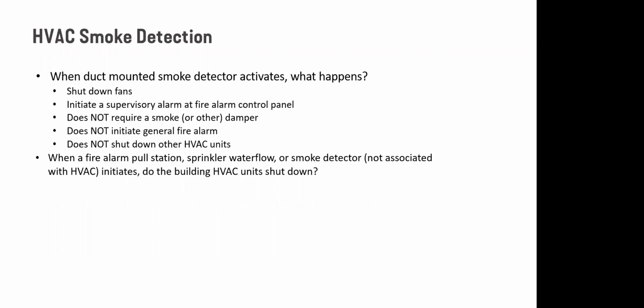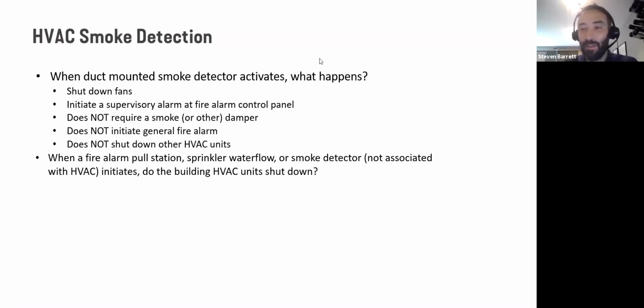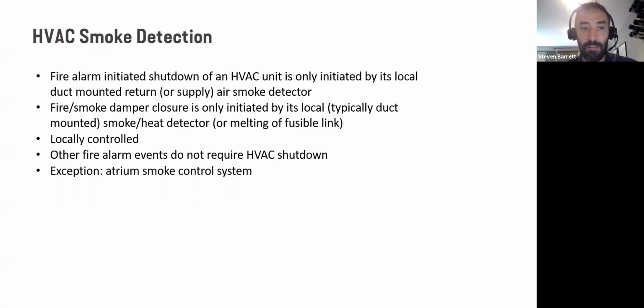We'll share the results of our polling. Cool. Well, you guys got that one right. No, we do not shut down the HVAC units when a pull station, sprinkler water flow, or smoke detector activates. We shut down the units when the associated detector, that is the duct detector within the unit on the return side or possibly supply side, is activated.